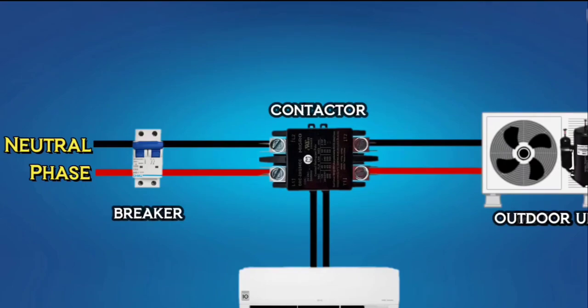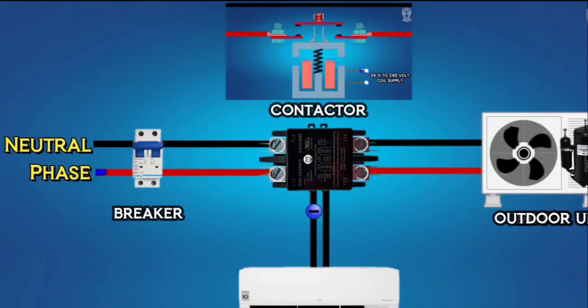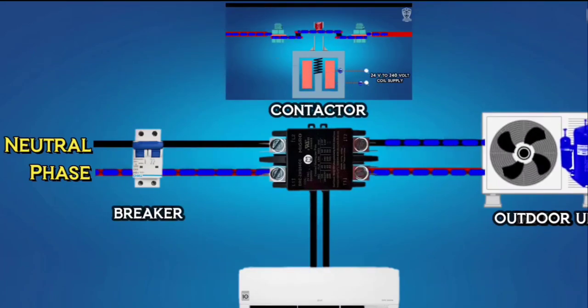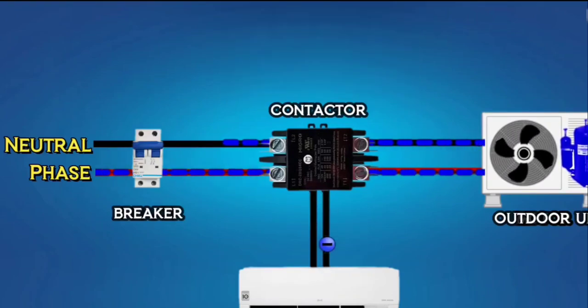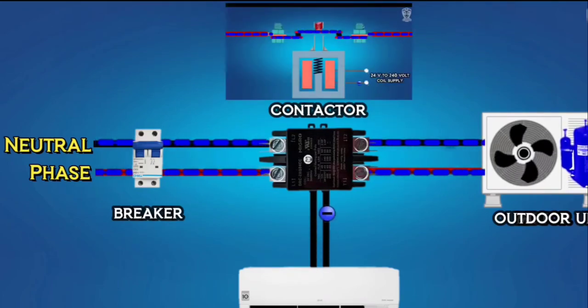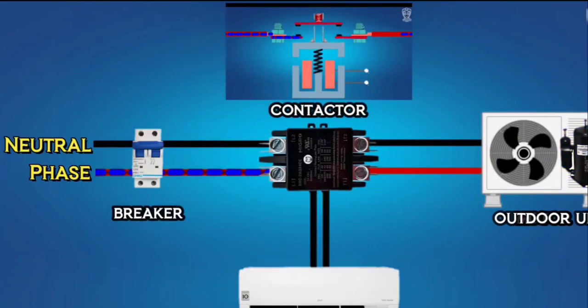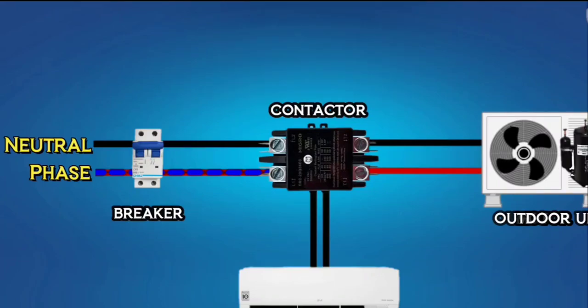Similarly, an AC unit also gives power supply to the outdoor unit through a contactor. When the room temperature is high, the PCB in the indoor unit sends a 24-volt power supply signal to the contactor. Through this, the contactor energizes and power supply flows. The compressor and fan motor start running. After the room temperature reaches the set point, the indoor unit will cut off the 24-volt power supply. Then, the contactor terminal will come to the normal position, and the outdoor unit will be cut off. This is how the contactor works.